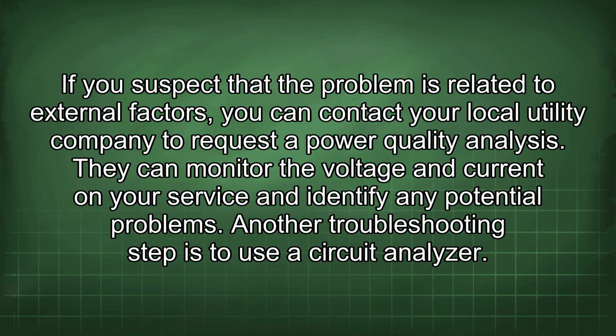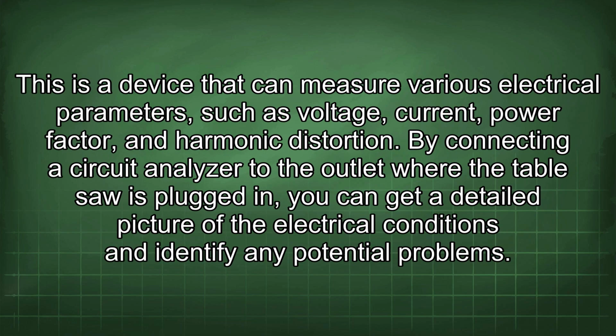Another troubleshooting step is to use a circuit analyzer. This is a device that can measure various electrical parameters such as voltage, current, power factor, and harmonic distortion. By connecting a circuit analyzer to the outlet where the table saw is plugged in, you can get a detailed picture of the electrical conditions and identify any potential problems.